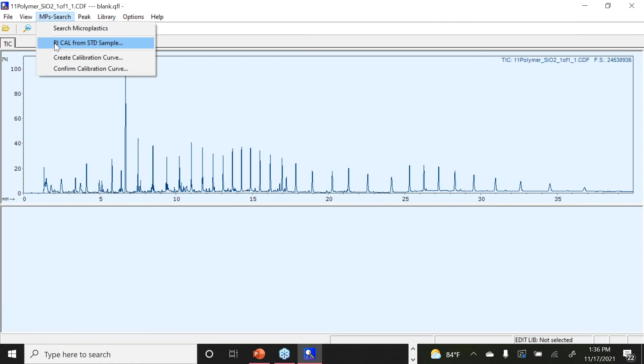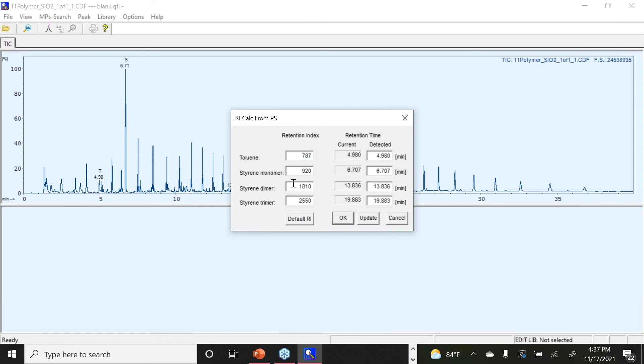So first step, as we discussed, we'll go ahead and do the retention index calculation from the standard sample. And here on the bottom, you can see that it was doing this for you. So these are the retention index calculations from the poly standard that are auto-generated. Now, if for any reason you want to go into more detail with your peaks and change, for instance, 4.980 to 4.90 or 4.982, you could do that, and it will automatically update for you. In this case, I'm just going to use the default auto-generated retention index from F-Search. Then the next step will be to create your calibration curve.